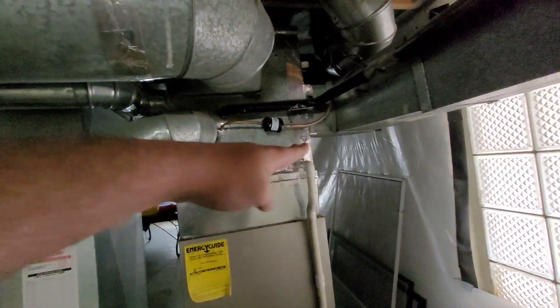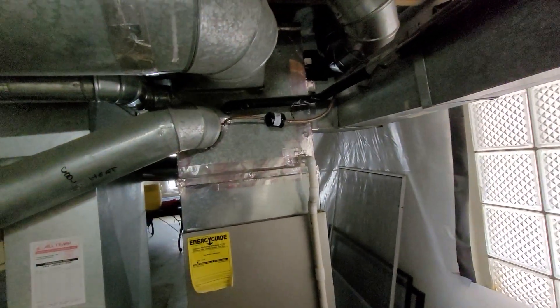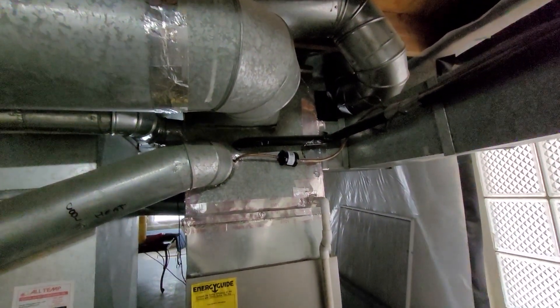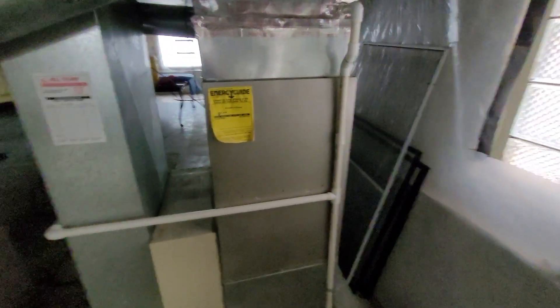The coil is way up in the plenum. We've got a takeoff on the front that we think is blocked — this is serving the second floor — and we think it's barring off a lot of airflow.